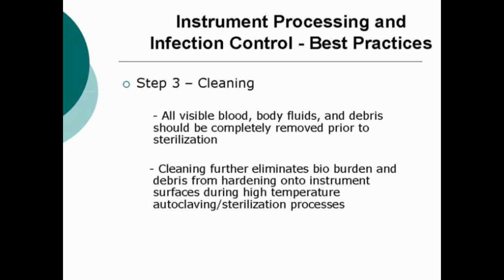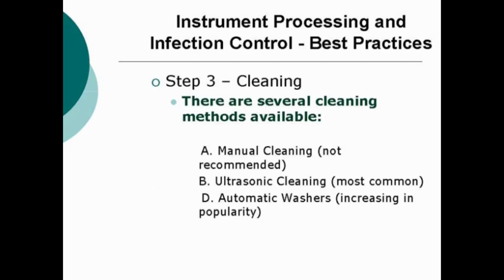Step 3 is cleaning. All visible blood, bodily fluids, and debris should be completely removed prior to sterilization. Cleaning further eliminates bioburden and debris from hardening onto instrumentation during high-temperature autoclaving sterilization processes. There are several cleaning methods available. Manual cleaning, which is not recommended due to the possibility of sharps injury. Ultrasonic cleaning, which is most common, and automatic washers. This is increasing in popularity within North America.